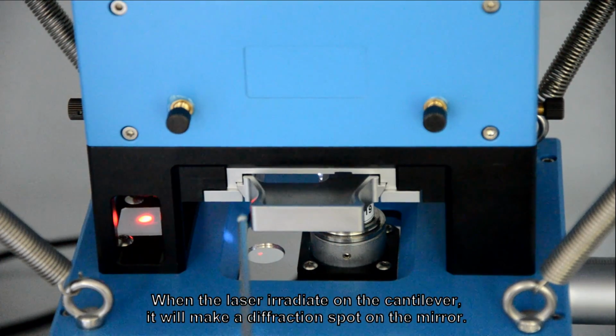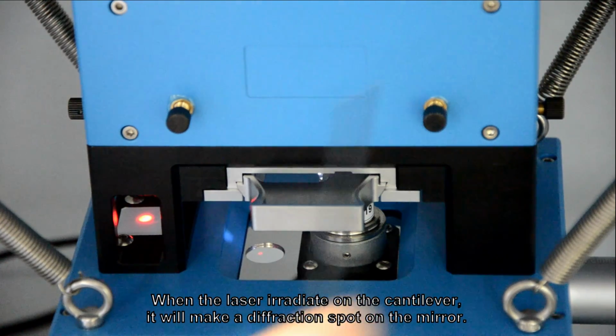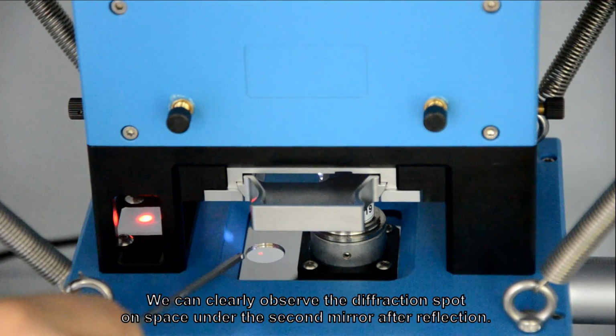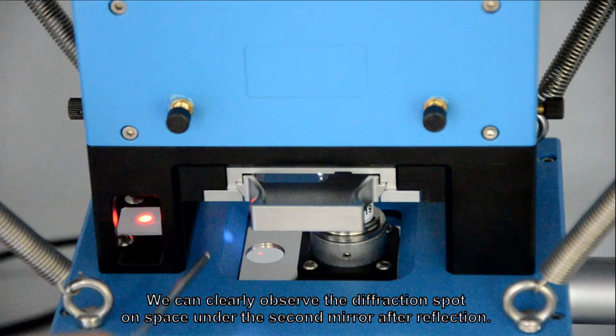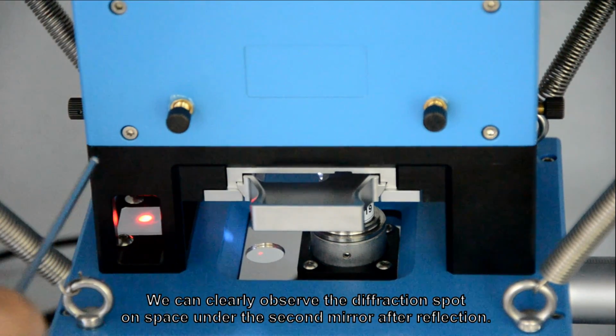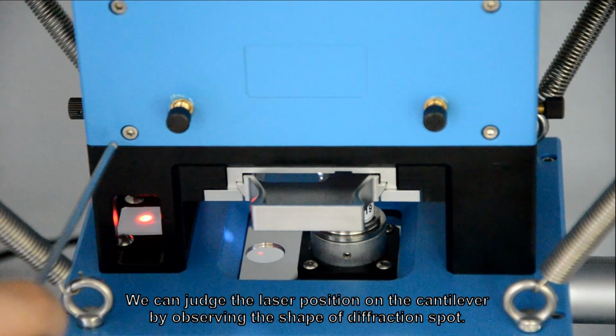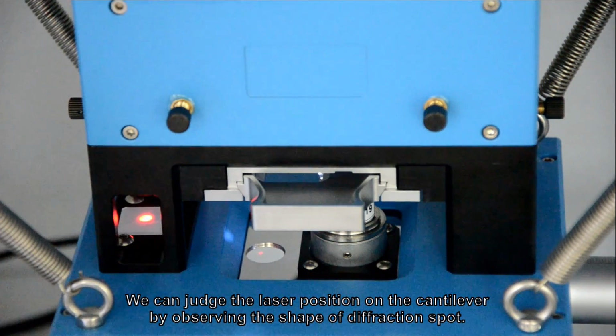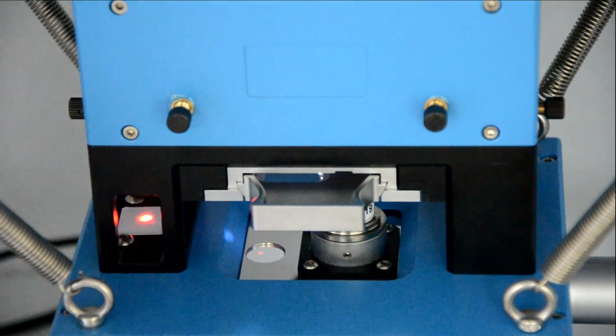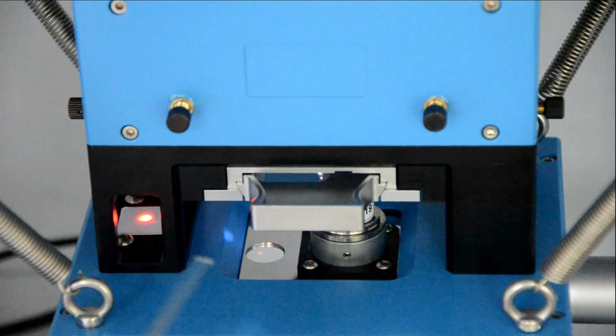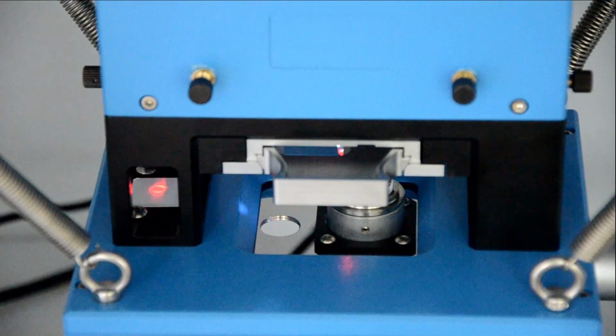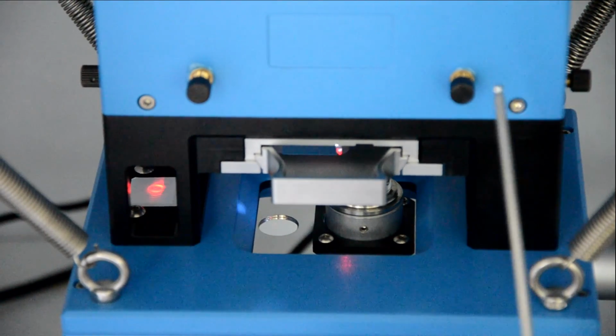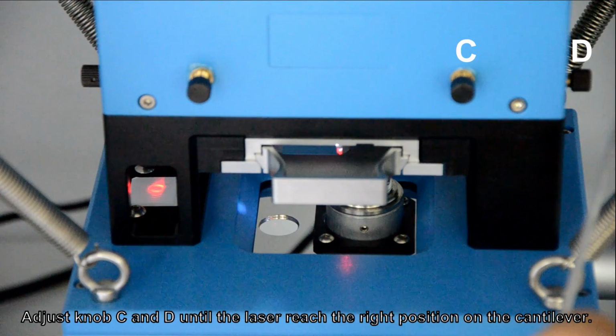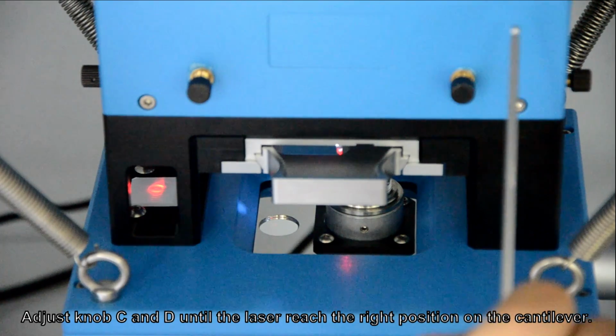When the laser irradiates on the cantilever, it will make a diffraction spot on the mirror. We can clearly observe the diffraction spot on space under the second mirror after reflection. We can judge the laser position on the cantilever by observing the shape of diffraction spot. Adjust knob C and D until the laser reaches the right position on the cantilever.